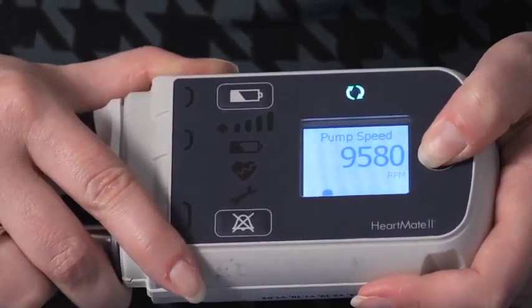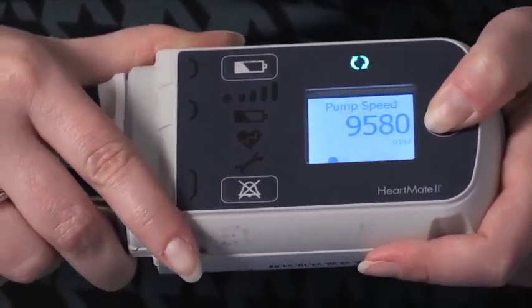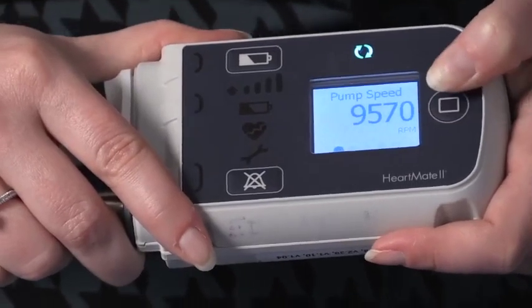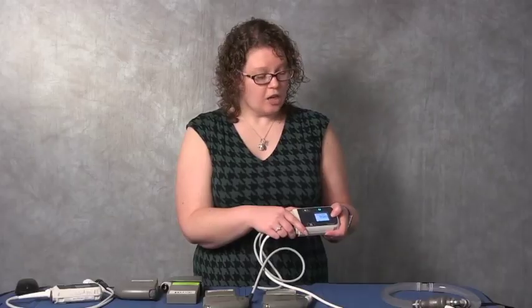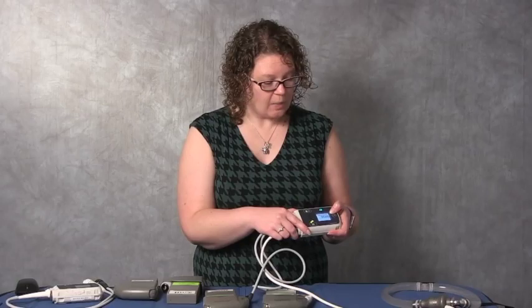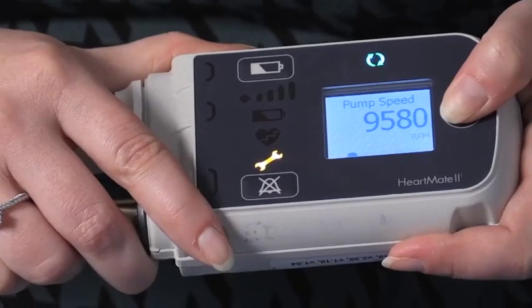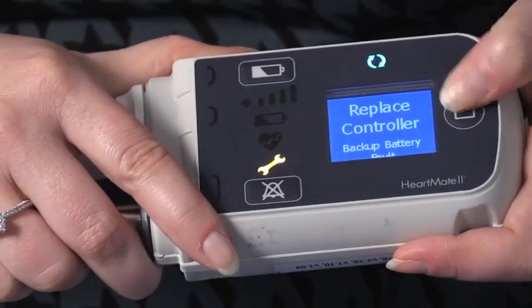The first number that comes up is the speed. We're measuring how fast that rotor is spinning. That is set for the patient, and it shouldn't vary, but by a little tiny bit. This pump is set at 9600. Currently it's running at 9590.